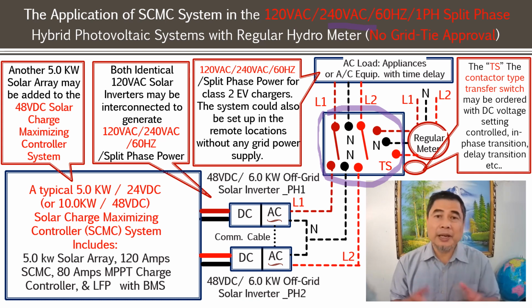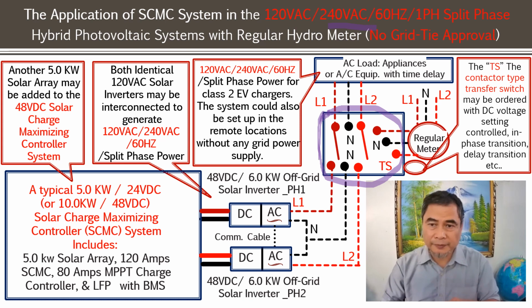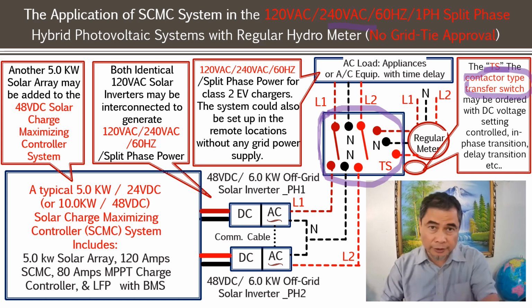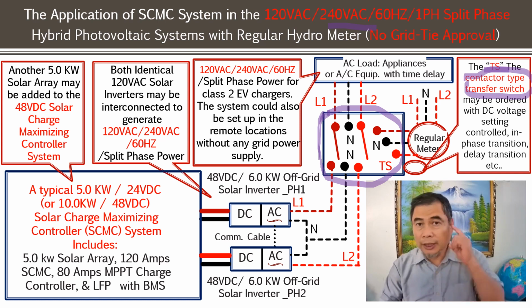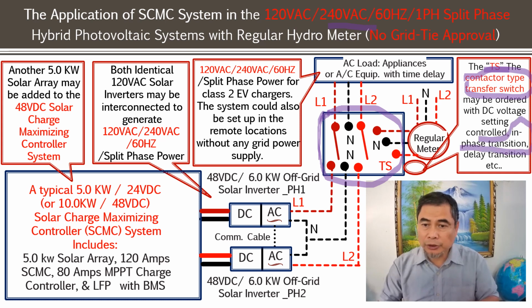But we don't have this kind of product available yet. But if you build this system, you have to go for a more expensive transfer switch from a different manufacturer. This contactor type transfer switch can have all these functions built in, with DC voltage sensing to transfer the load. It can also have the in-phase transition built in to make sure the motor appliances, the AC equipment, can run without problem.